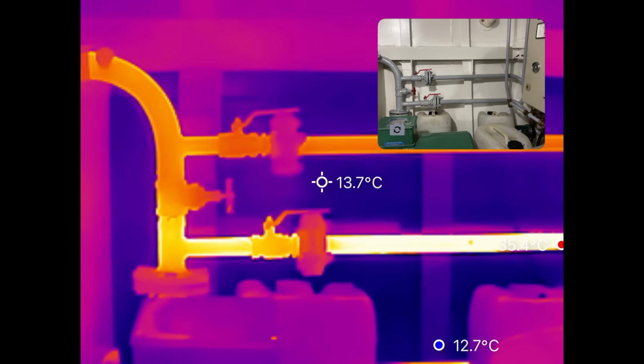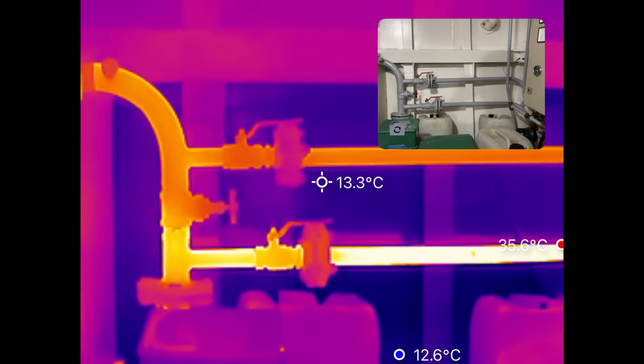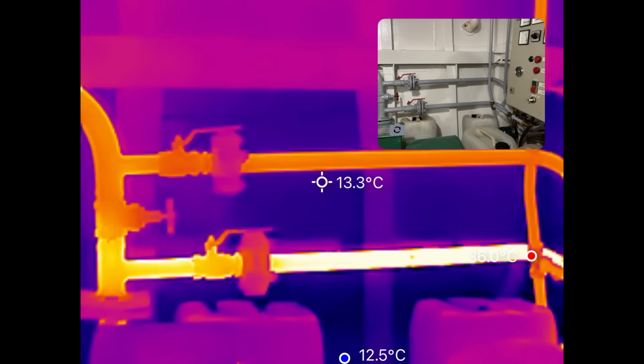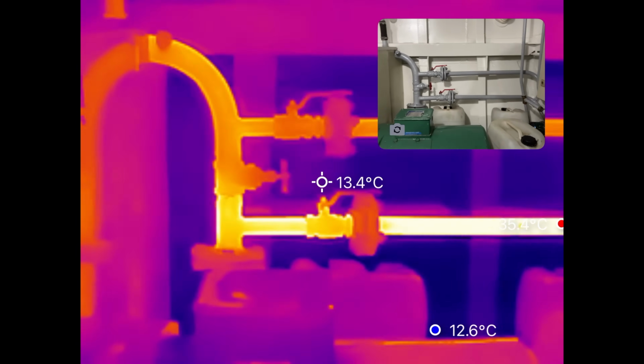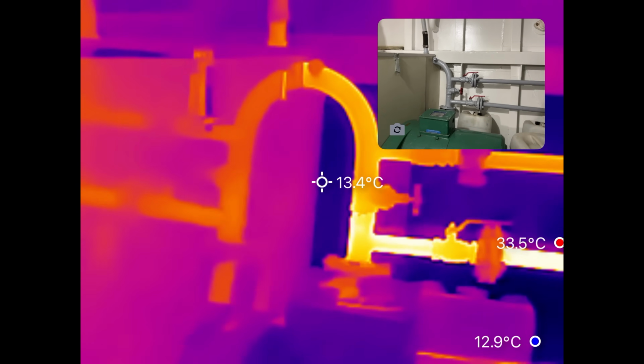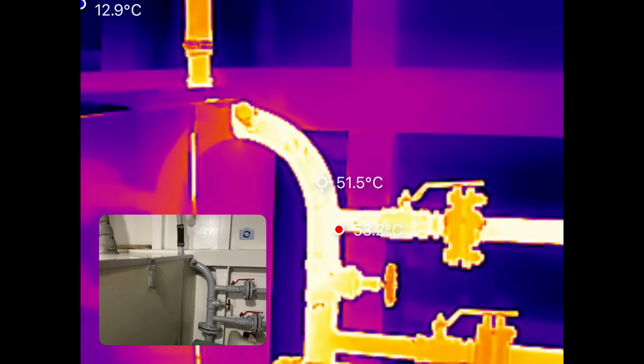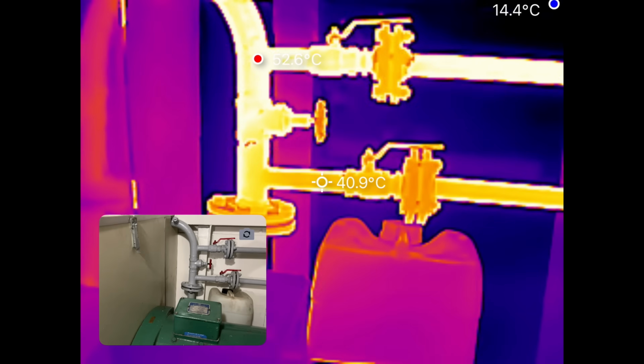At first we see that the return line becomes hot, which makes sense because just after startup the buffer tank is hotter than the engine coolant. After a while, when the generator is warmed up, we can see that the supply line has become hotter than the return line, so it's transferring its heat to the buffer tank. The coolant branch from the main engine still has to be tested and fine-tuned. But for now, we are ready for wintertime.